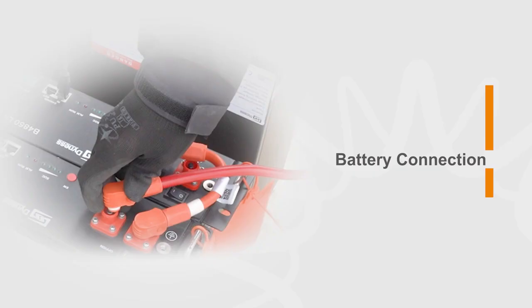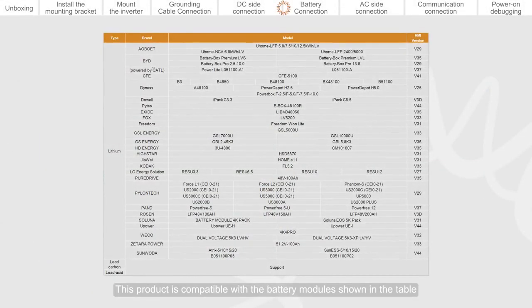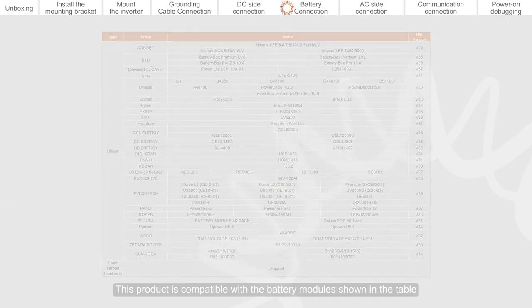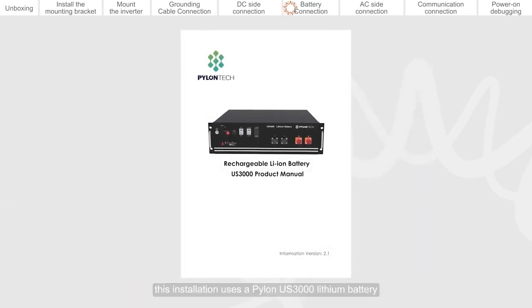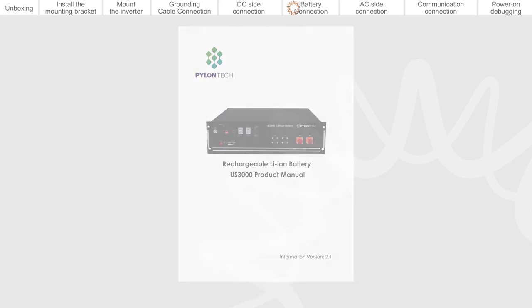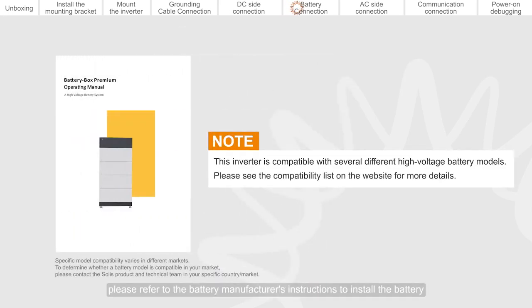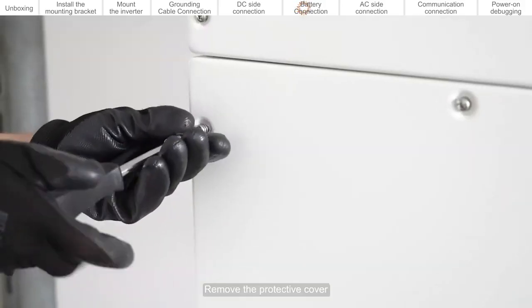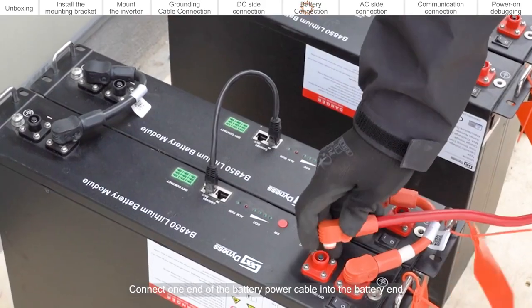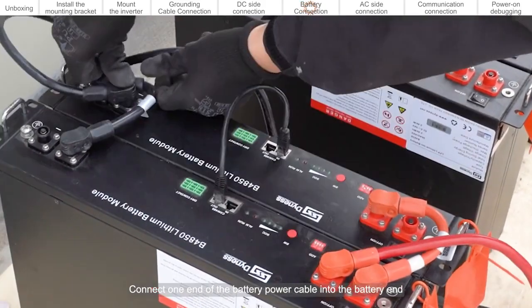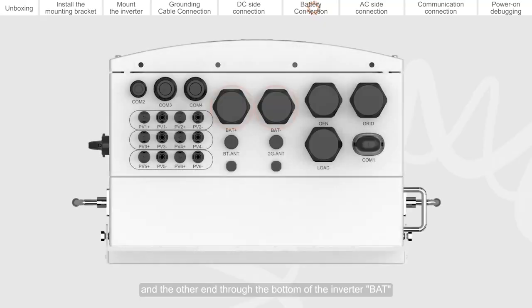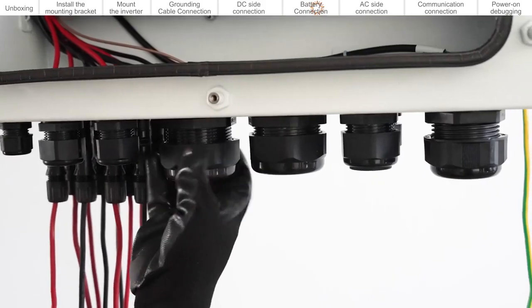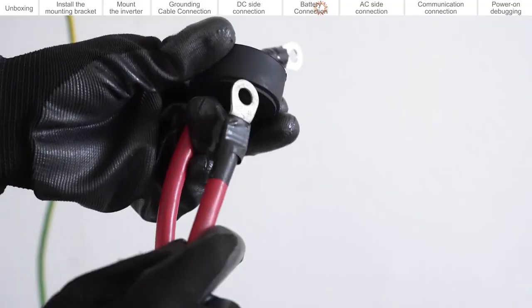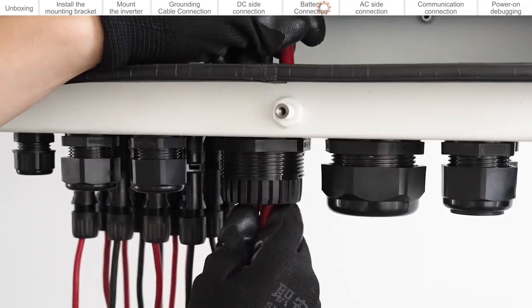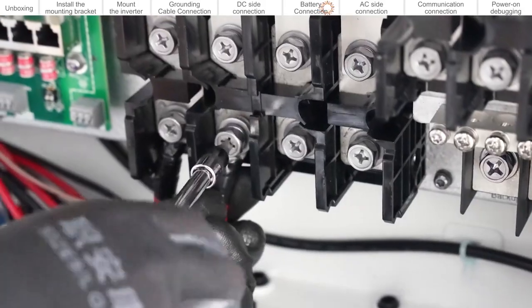Battery connection. This product is compatible with the battery modules shown in the table. This installation uses a Pylon US3000 lithium battery. For battery installation, please refer to the battery manufacturer's instructions to install the battery. Remove the protective cover. Connect one end of the battery power cable into the battery end and the other end through the bottom of the inverter bat. Connect to the corresponding port.